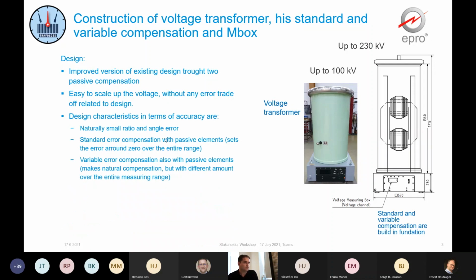Generally speaking, inductive voltage transformers are very stable over time in terms of error and naturally have a low error. In addition to that, we use so-called standard error compensation, and especially for this project, the variable error compensation. The standard error compensation is often used, and its job is to set a naturally small error around 0 in value and angle. This kind of compensation is constant in its value over the entire range. That means that you can only slide the error back and forth.